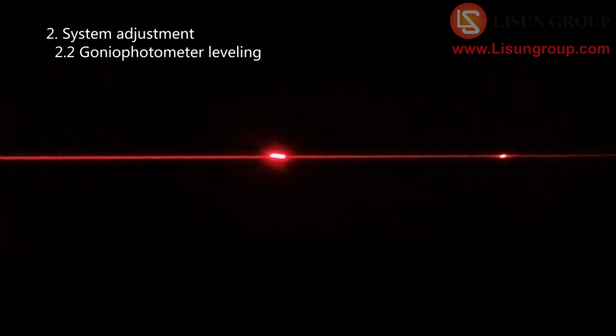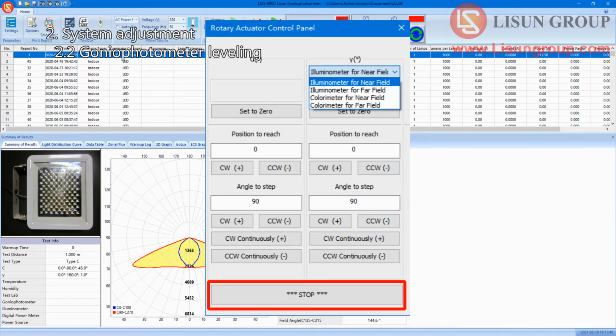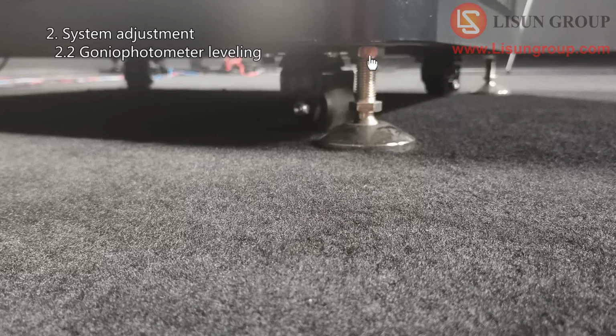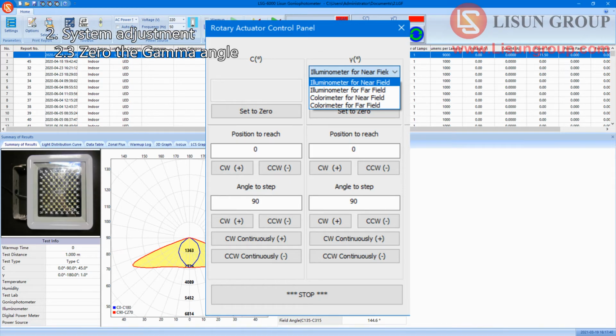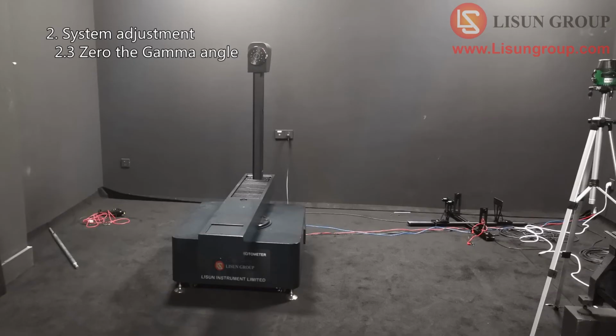All the 4 feet need to touch the ground firmly after the adjustment. Sufficient patience is required to adjust this step. Click the stop button to stop the rotating after the adjustment. Turn the screw up to secure the feet. Choose Illuminometer for near field. Input 0 here. Click any one of these 2 buttons to rotate the goniophotometer. The main arm will stop at 0 degree position when it stops rotating.